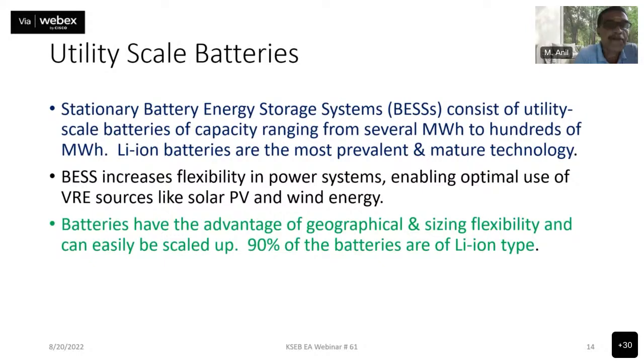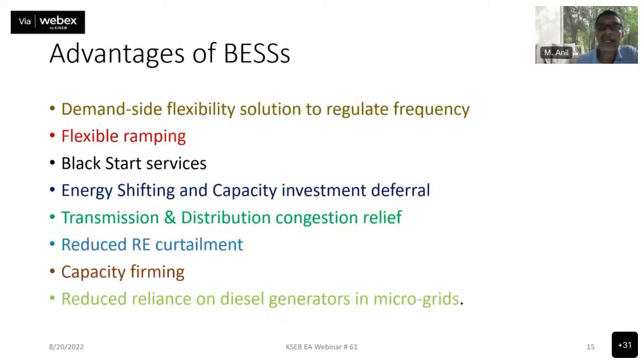So batteries have the advantage of geographical and sizing flexibility and can be easily scaled up. That is, we need not have any geographic speciality for the area for proposing a utility scale battery at a particular point in a substation or something of that sort. That's why, irrespective of the geographic conditions, we can utilize batteries, and 90% of the batteries are of lithium-ion type. Advantages of battery energy storage systems.